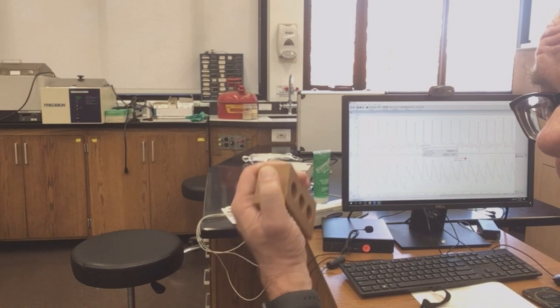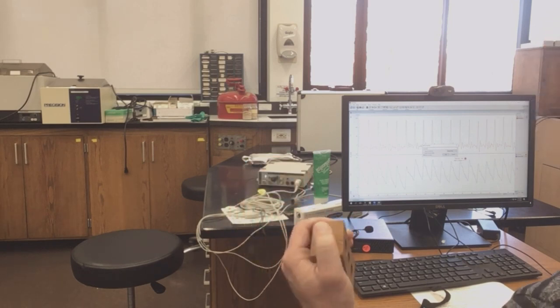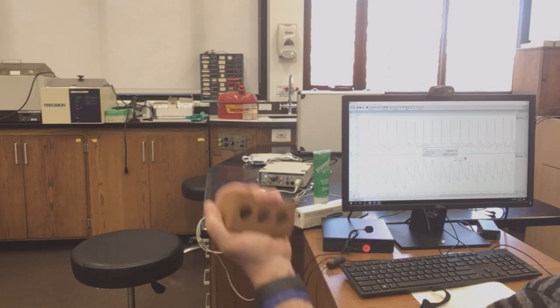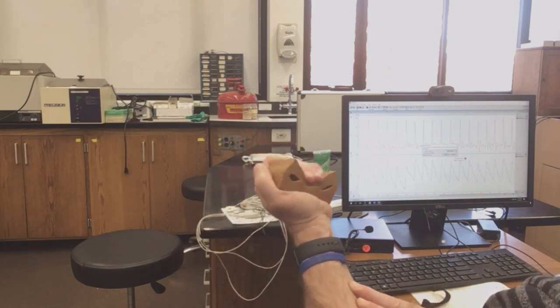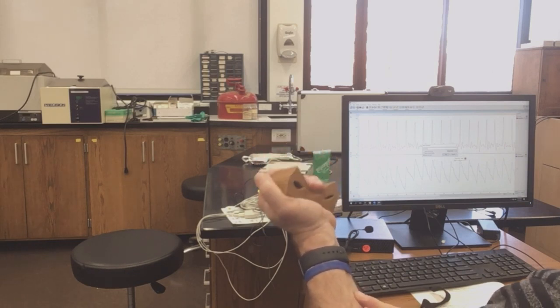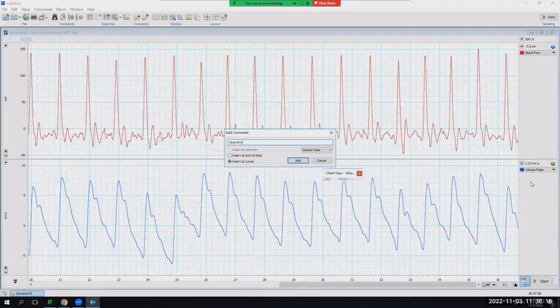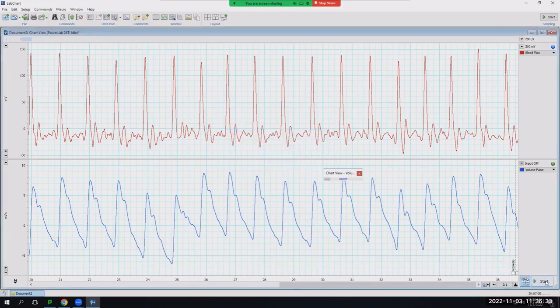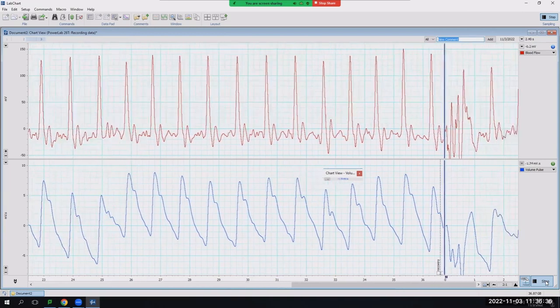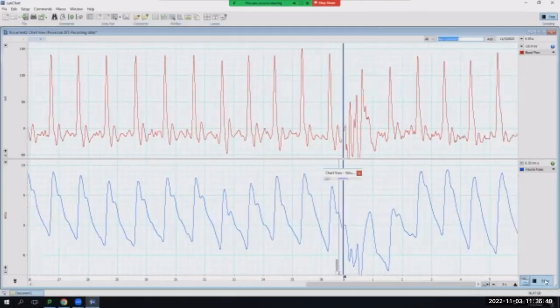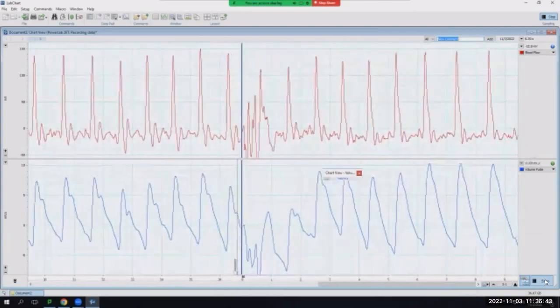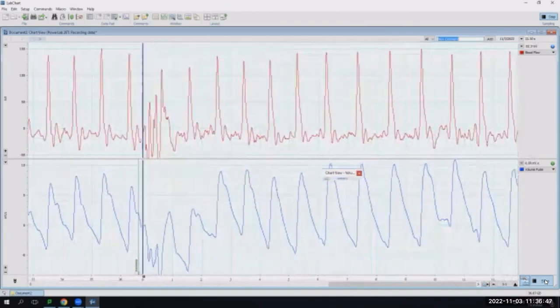In fact, you should probably take the pulse transducer off. You want the individual to be squeezing an object for 3 minutes to do this set of hand exercise, and it should ideally get the forearm muscles very active, ideally to the point where they start to fatigue. Once the individual has exercised their hand for 3 minutes and fatigue has started to set in, reconnect the pulse transducer to the middle finger like before, add the comment that says recovery, and then hit start.